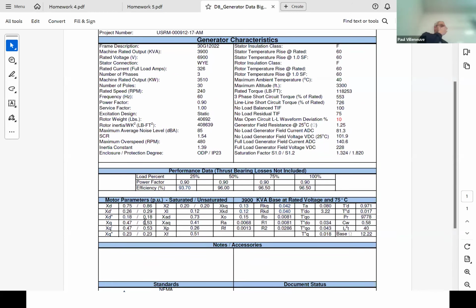So for generators, you need to have both of those parameters because you need to determine what characteristic you need to use when you're running, saturated or unsaturated. Interestingly enough, it only affects the X values. It doesn't affect the R values at all because that's resistance, right? Magnetic energy has no impact on that. It's just going to be the value of X. So again, you can see a real world application with an actual data sheet.